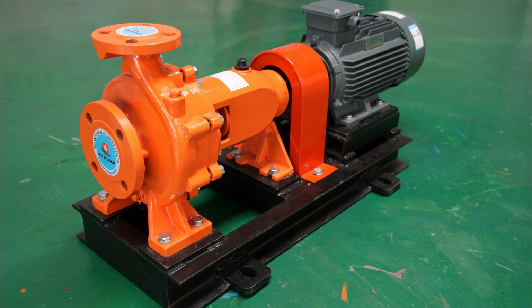What about more technical issues that can affect flow? There's something called net positive suction head, or NPSH. In simple terms, it's basically the pressure available at the pump's suction side. If that pressure's too low, the pump can't draw in enough fluid, and that leads to reduced flow. One trick is to shorten the suction pipe, which can sometimes help improve the NPSH.